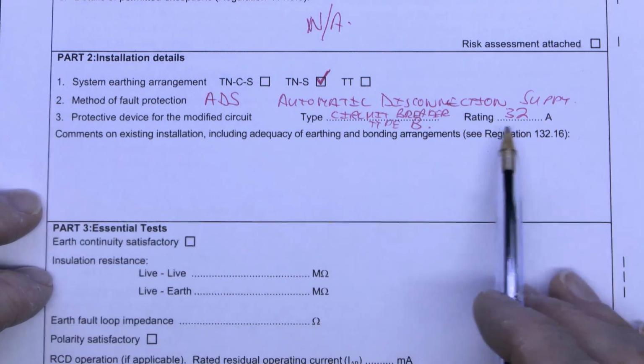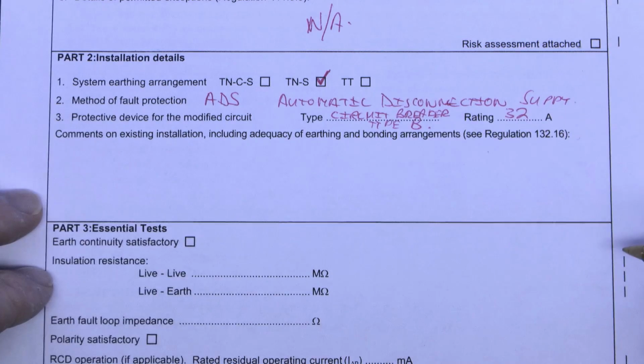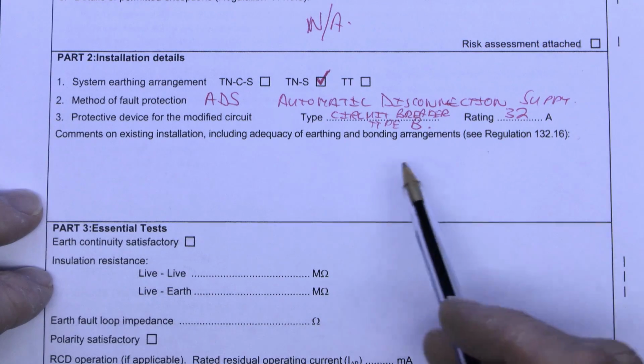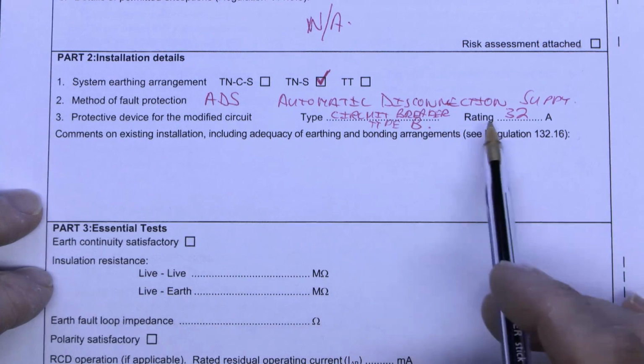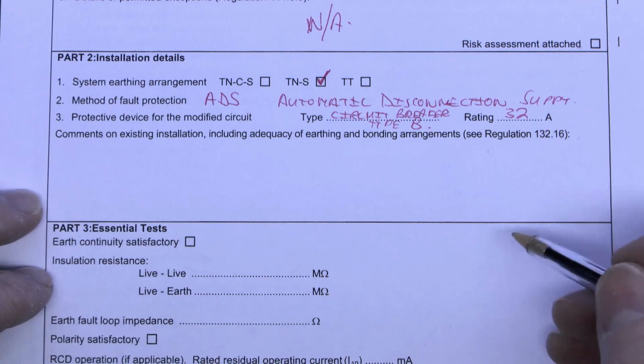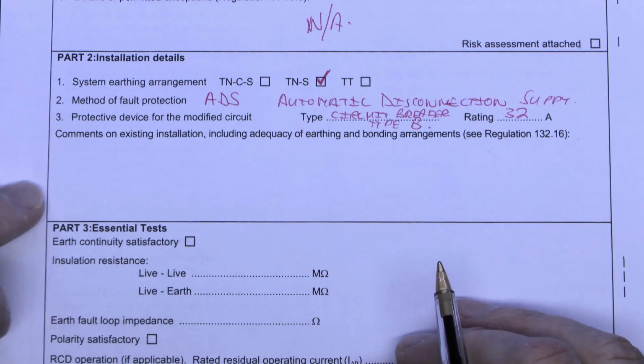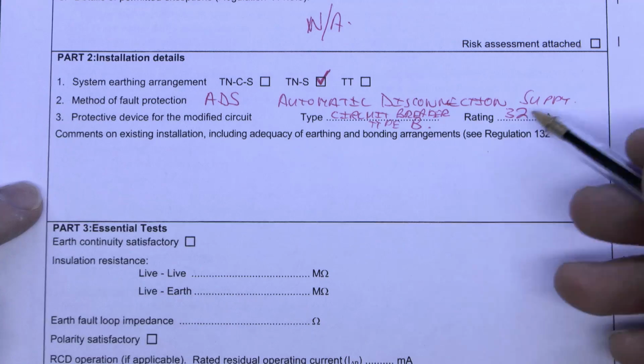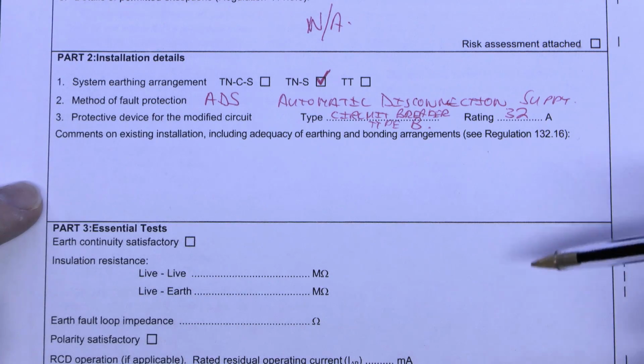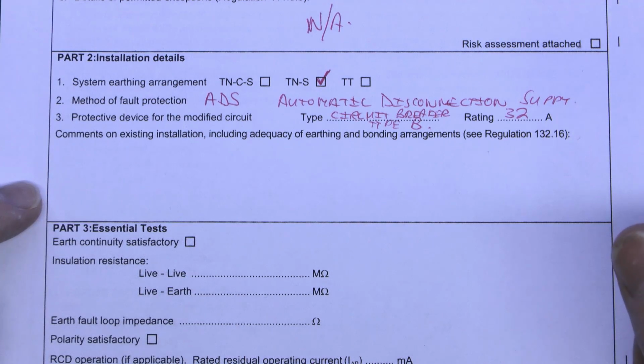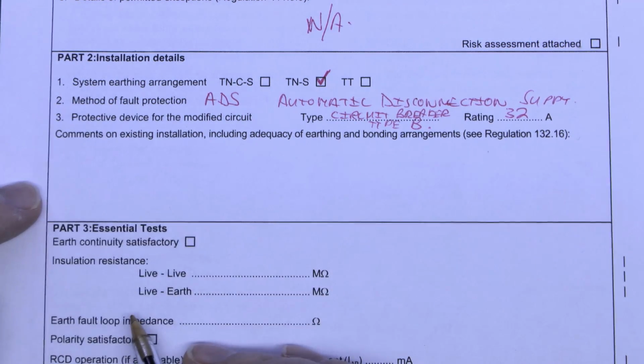So in this case, 32 amp circuit with the ring there, that's no problem. But if you got somewhere and found that someone had an old fuse system and they just shoved a piece of nail or something in the fuse instead, pretty obviously that's not going to be suitable. And likewise, if you found that the circuit breaker was, say, a 63 amp job on a lighting circuit, well, again, pretty obviously that's not acceptable either. So this is really just a description of things, just to confirm that you did actually look there.